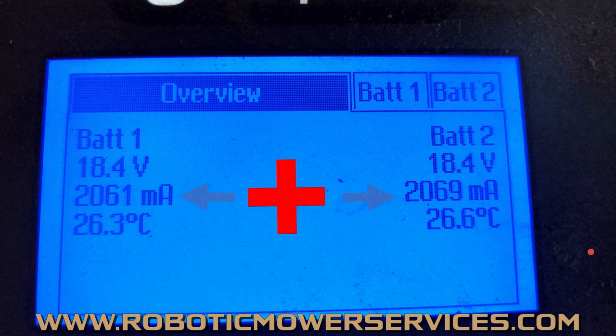Because if you look at this right here, obviously we're working with a 450 because we have battery one, battery two, and we have charge current coming into both batteries. We have 18.4 volts coming into both batteries, so we have good voltage coming in. But we have 2,061 milliamps coming into one battery, 2,069 milliamps coming into the other. We can go up to 7,000 on here. We need a minimum of 5,600. That's our 80% of 7,000.